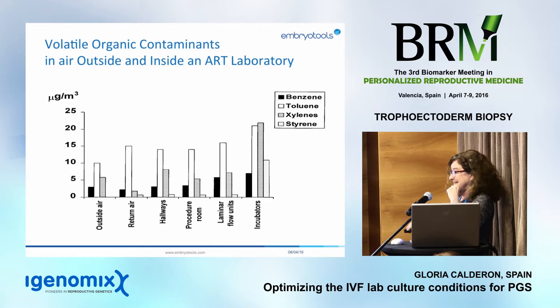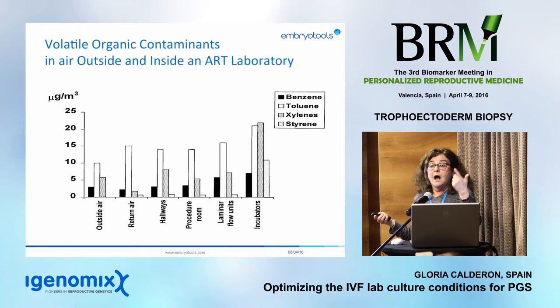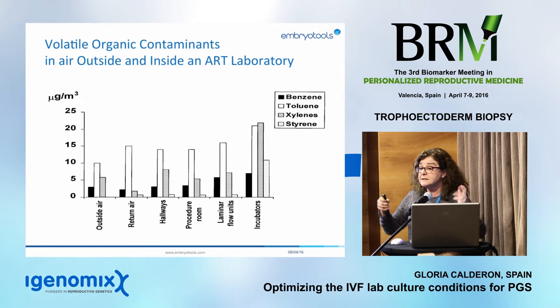Jacques Cohen also analyzed the amount of four VOCs in different parts of the IVF facility. Surprisingly, outside air was the cleanest — the amount of these four VOCs was much lower than inside our incubators. It is the lab, the equipment, the plastics, oil, temperature, and humidity that disturb our air quality. Incubators at 37 degrees, hypersaturated with humidity and full of plastic, outgas VOCs completely. It's also good practice to use VOC/HEPA filters inside older incubators, as they accumulate VOCs over 10–15 years.